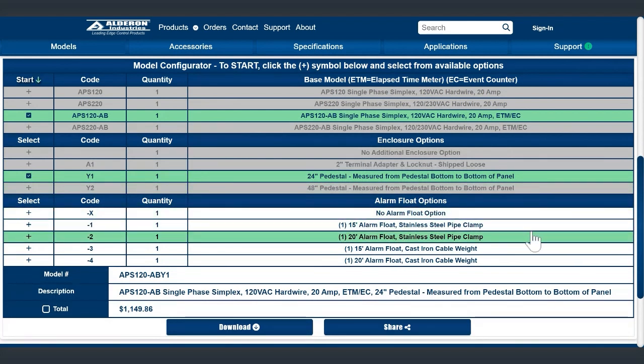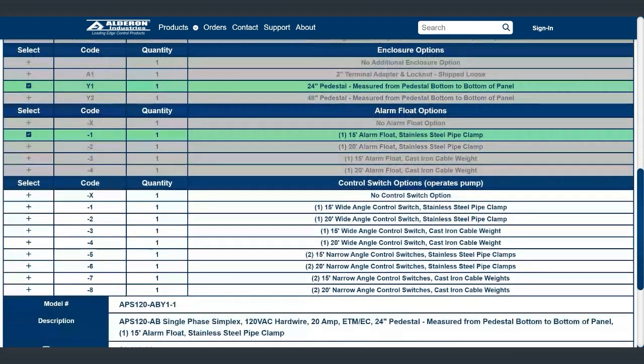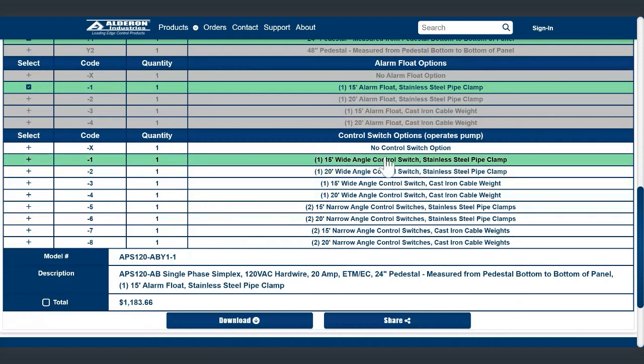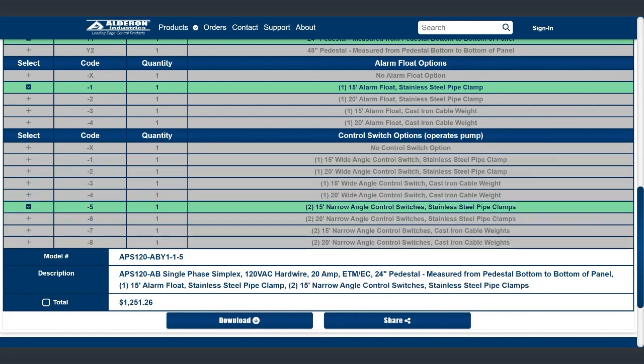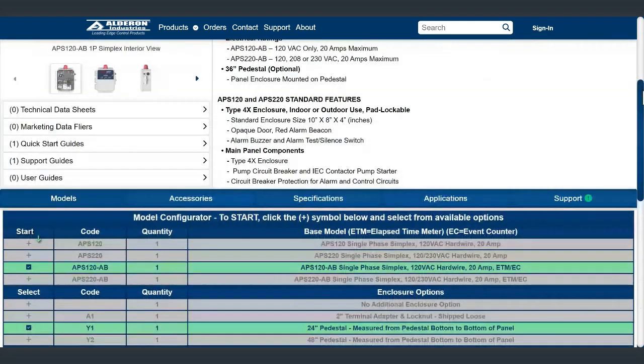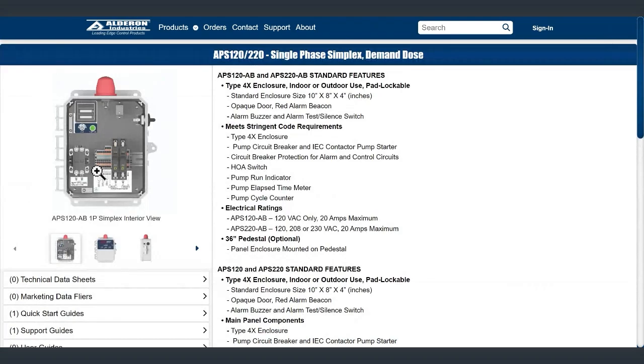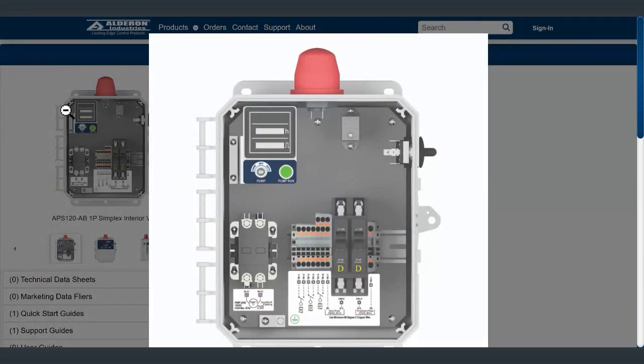So let's say we do that. You can get it with alarm floats, cable weights or pipe clamps, 20 foot or 15 foot. And you can do your control switches, you can do wide angle or narrow angle, depending on how quickly or how much pumping range you want. If you want just a real narrow angle pumping range, if you want to do kind of micro doses out to your field, you can pick the narrow angle. Or if you want a wider angle, get more volume out at a time, you pick that. We'll do the narrow angle 15 foot. And there you go. So you get your list price there. That's kind of what that looks like for everybody remotely.